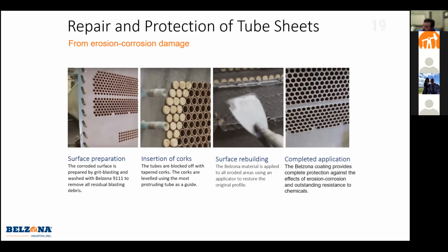You can see in that third picture from your right, we'll use that as our guide. Especially on roller expanded tubes that stick out 1/8 to 1/4 of an inch, that gives you even more Belzona material to erode away in place of your metal. All the way on the right, you can see our completed application with our 2-coat system of ceramic epoxy, after we pop the corks out and hone the tubes back for you.